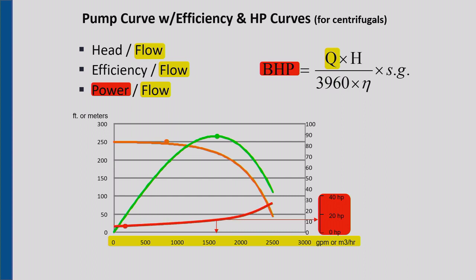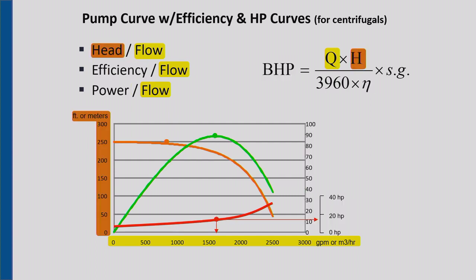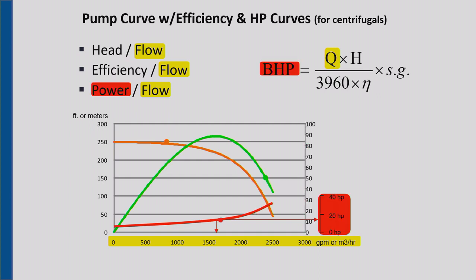Vertical turbine pumps tend to have what we call a mixed flow impeller, which is somewhere between a centrifugal and an axial flow. So while this pump curve and a lot of pump curves illustrate higher flow equals higher load, on vertical turbine pumps that may or may not be true. Okay? You got to look at the pump curve and see where it is. And that curve will be on any pump curve that you've got, there will be one that represents the power. And that'll tell you how much power that pump needs at any given flow and head.